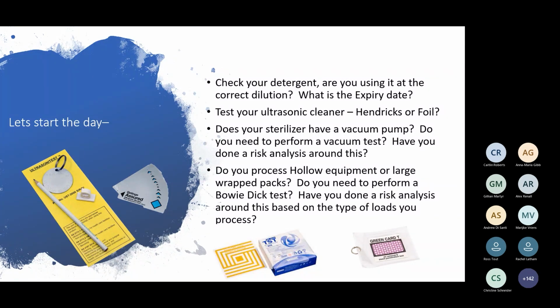The RACGP guidelines basically say that you need to test the ability of your machine to pass the vacuum test. So that's why you're doing a vacuum test. And you can basically do a risk analysis around it. I've got some written out risk analysis a bit later. Basically saying you're performing the vacuum test, the capability of the machine. You don't process any hollow instruments. So you can just do the vacuum test once a week. And then maybe set it on Monday mornings, you do your vacuum test. If you have a B-class sterilizer, you may need to do that vacuum test every day, especially if you are processing hollow A type instruments or large packs. You may need to do Bowie-Dick tests.